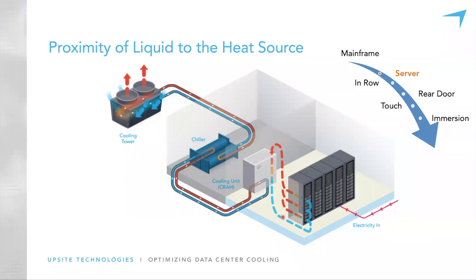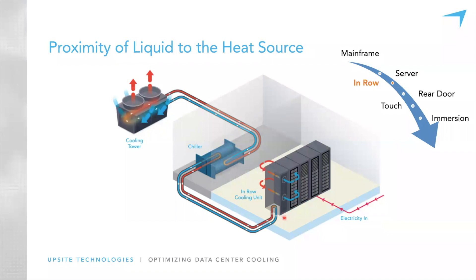Moving on to in-row cooling: instead of having the cooling at the perimeter of the room, we move the cooling closer to the load. A small cooling unit sits in the row of cabinets. Air from this cooling unit serves all the IT equipment in the row, picking up heat and bringing it back to the cooling unit, where a heat exchange process passes the heat to liquid, which then carries it out of the building. The liquid has moved a little closer to the heat source.